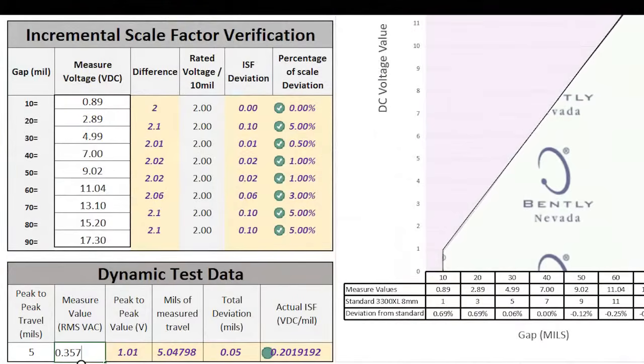Record the average value. If you are using my spreadsheet, simply plug the numbers into the dynamic test table. The spreadsheet will automatically calculate the voltage measurement and provide you with the actual measured travel, as well as the deviation from the standard. A pass or fail condition will be flagged using a green light or a red light.